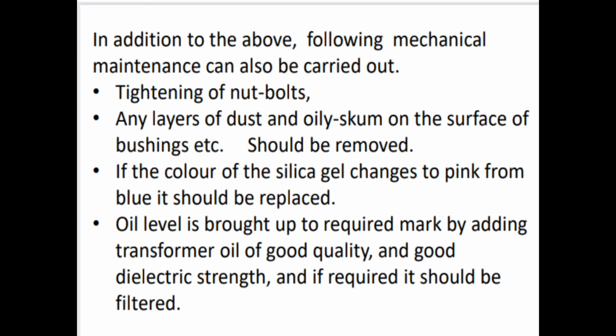So, in addition to the above, the following mechanical maintenance can also be carried out. Tightening of nut bolts, any layers of dust and oily scum on the surface of bushing, etc. should be removed. If the color of the silica gel changes to pink from blue, it should be replaced. Oil level is brought up to the required mark by adding transformer oil of good quality and good dielectric strength, and if required, it should be filtered.